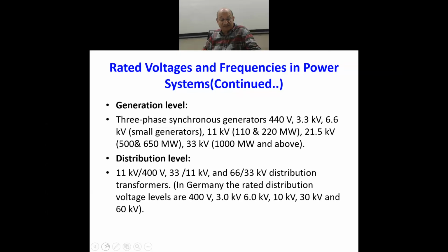In fact, the multiple of 33 kV is the system initiated by the British, and we have also followed that system in our country. But you would be surprised to know that, for example, in Germany, the system is 400 volt, not 440 volt, and 3 kV, 6 kV instead of 3.3 kV or 6.6 kV, as you can see. So it is a multiple of 10, not a multiple of 11. This question I have been asked very often, why this multiple of 11 is considered standard in our country. But it is not that it must be followed all throughout.